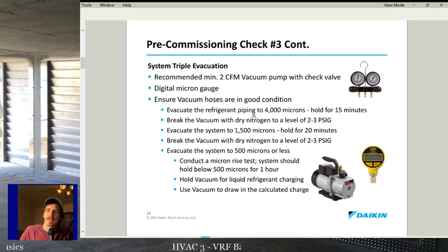Good digital micron gauge. Ensure your hoses are in good condition. Ensure your gaskets are good. And what they don't tell you here, but I will tell you guys, is Nylog. Nylog is your friend. So when you're vacuuming, put a little bit of Nylog where all your hoses and everything connects, or if you're using solid copper, where your copper lines connect to your system. Put a little Nylog on those flares and you will have a much better time of it. It helps way more than you would think. Alright, a little bit of Nylog.